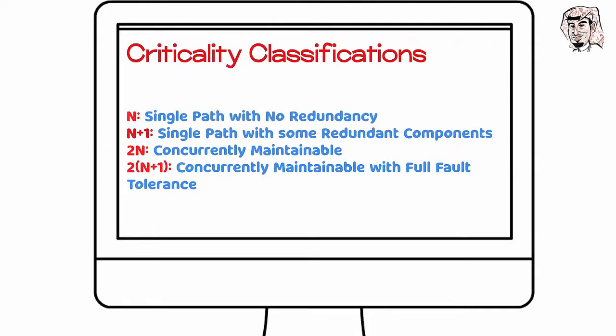Criticality classifications. N is single path with no redundancy. N+1 is single path with some redundant components, while 2N is concurrently maintainable. Finally, 2N+1 is concurrently maintainable with full fault tolerance.